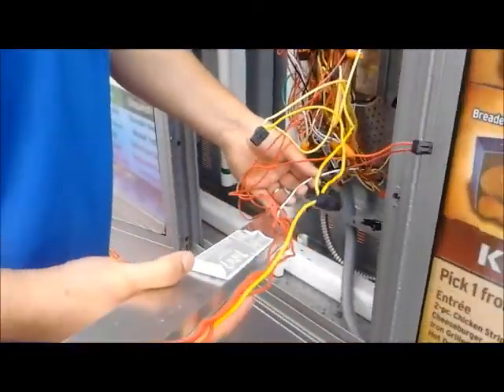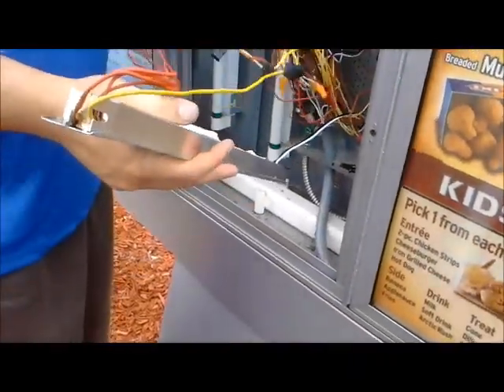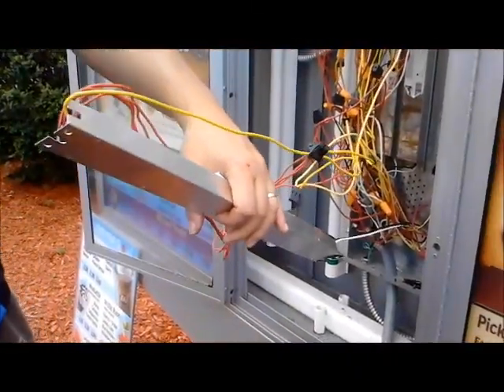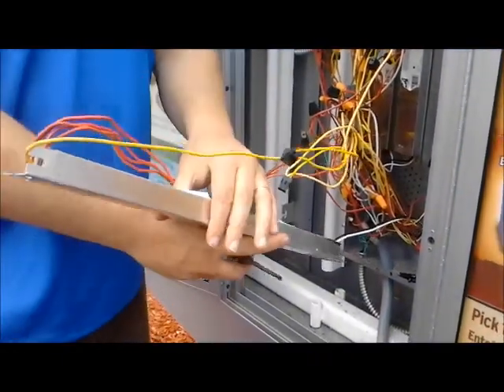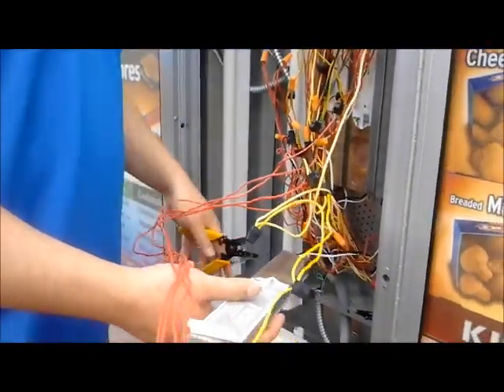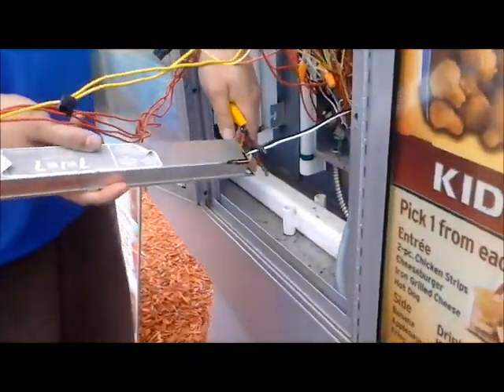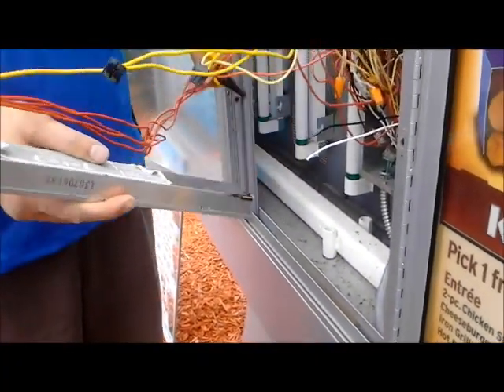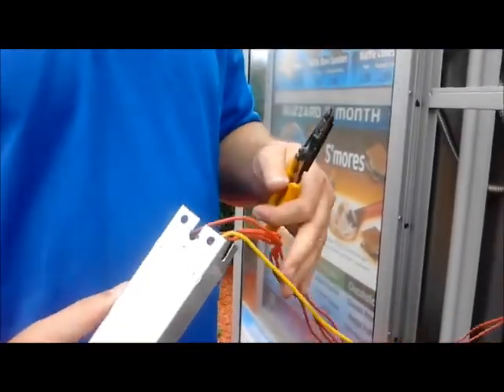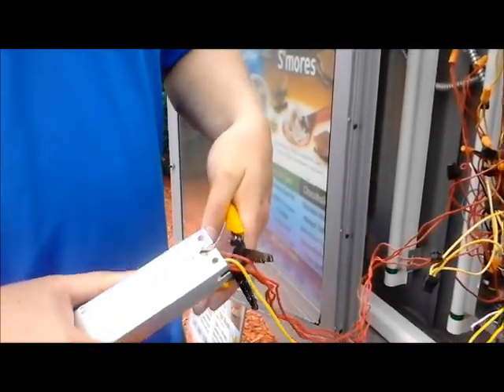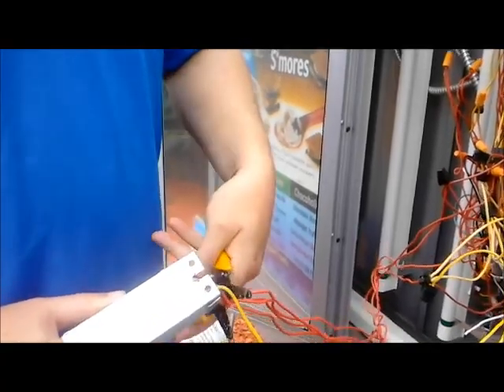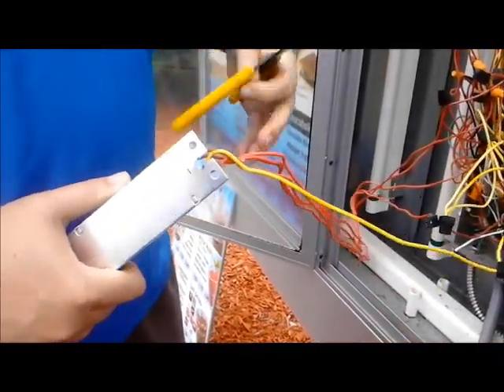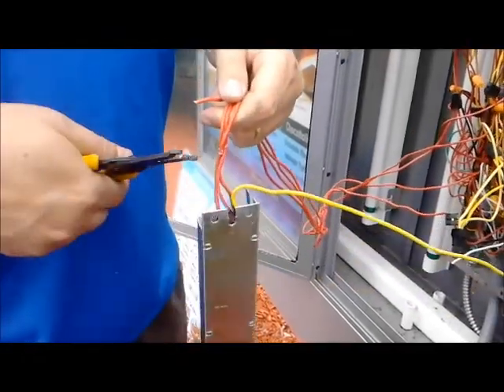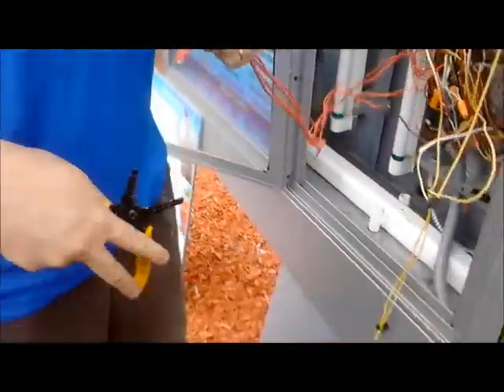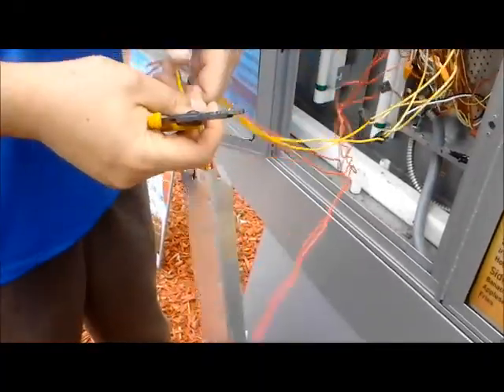Now you've got to be careful. If your menu board was on, this ballast is going to be extremely hot, so be careful you don't burn yourself. But what we're going to do is grab our wire cutter. You're going to slice the wires in several places. First, slice it as close as you can to the white and black wire, and then slice it as close as you can to all four red wires here. And then you're going to slice the yellow wire out. Generally, it's a good idea to take it one at a time and not dent the front of your menu board doing it. All right, so we're going to get rid of that ballast.